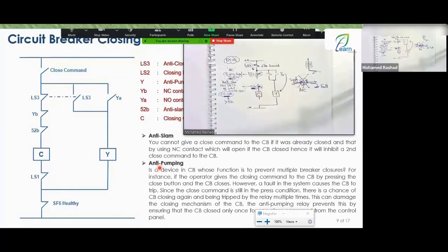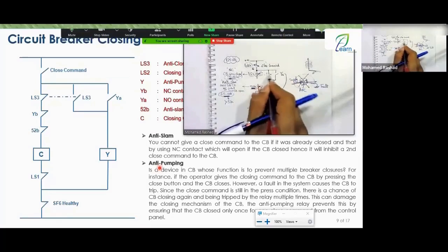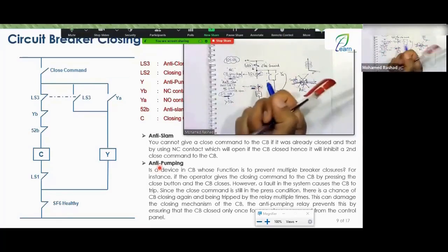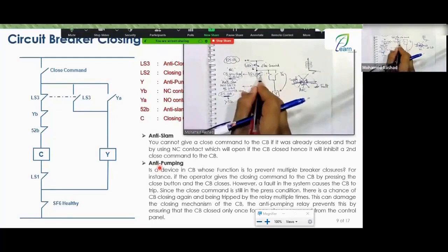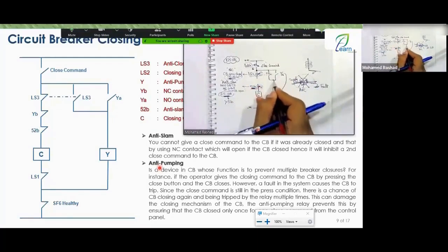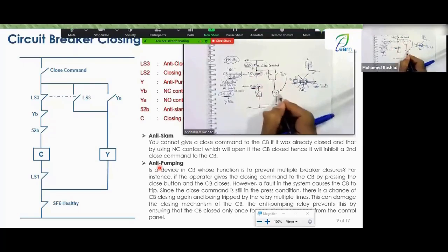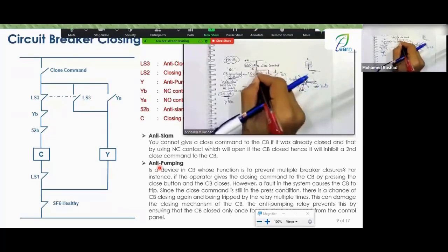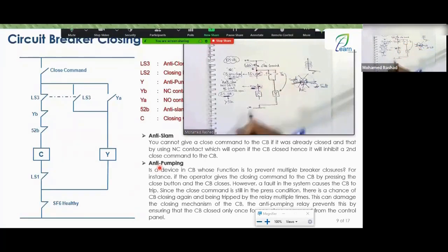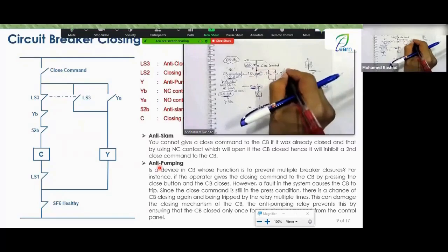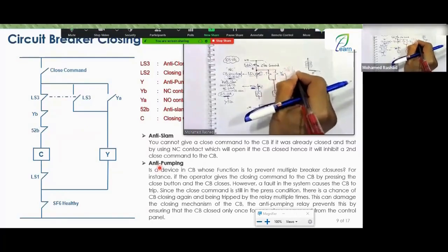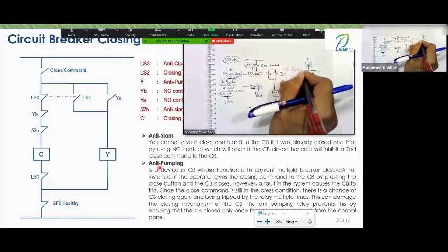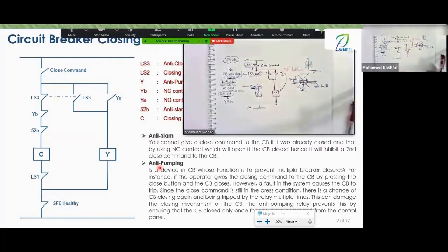But you have to say, what is this, Engineer Rashad? When this opened and that closed, after you closed the breaker, the spring discharged. So this opened and that closed, connecting the DC here. Now, there is a positive here and a negative from below. So this worked and closed on itself, and the situation remains like this, always closed. This received a supply. So what did it do? It performed something called self-latching, meaning it latches itself or holds itself. We call it self-latching.